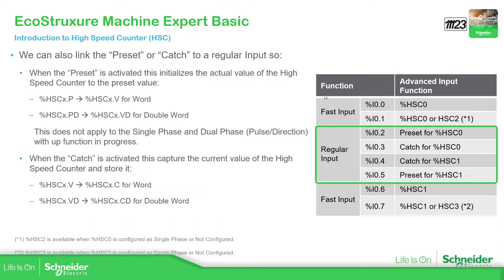At the fast input, there are some additional items you can configure: the preset and the catch. You can assign the preset and catch configuration to digital inputs, so you don't have to use the software if you don't want to. If you want to use the preset, you can assign one of the digital inputs, and depending on which high-speed counter you are using, you must assign to that specific input — the software will tell you which one to use.